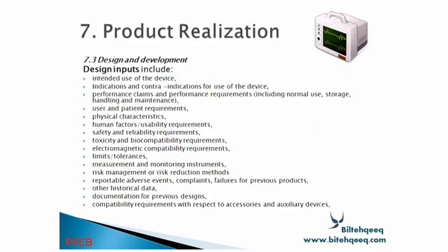And design input includes intended use of the device, indication and contraindications for use of the device, performance claims and performance requirements including normal use, storage, handling and maintenance, user and patient requirements, physical characteristics, human factors, usability requirements, safety and reliability requirements, toxicity and biocompatibility requirements, electromagnetic compatibility requirements, limits, tolerances, measurements and monitoring instruments, risk management or risk reduction methods, reportable adverse events, complaints, failure for previous products, other historical data, documentation for previous design, compatibility requirements with respect to accessories and auxiliary devices.